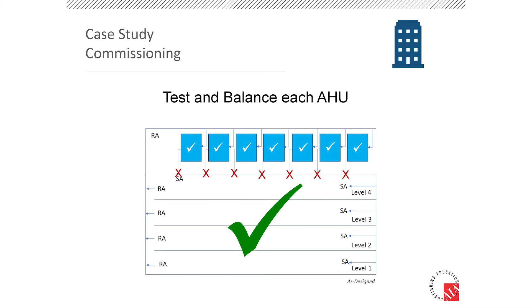After it was tested and balanced, we'd check that particular unit for safety and general functionality. Couldn't do capacities technically yet, we'd have to revisit that later. And as more and more doors were closed on each unit, we would test them in turn. That would give you some assurance of reliability because we've tested the sequence of operations on it.